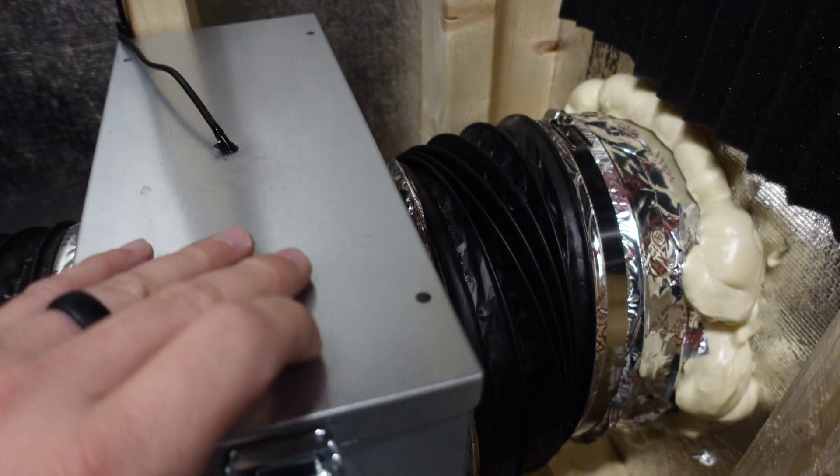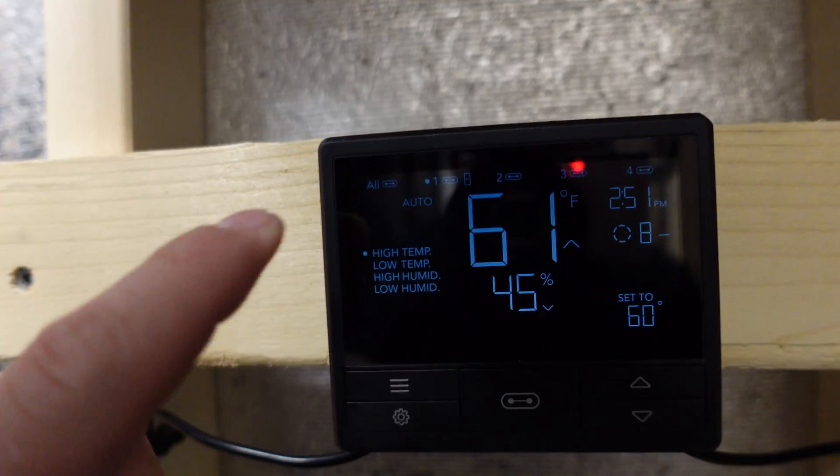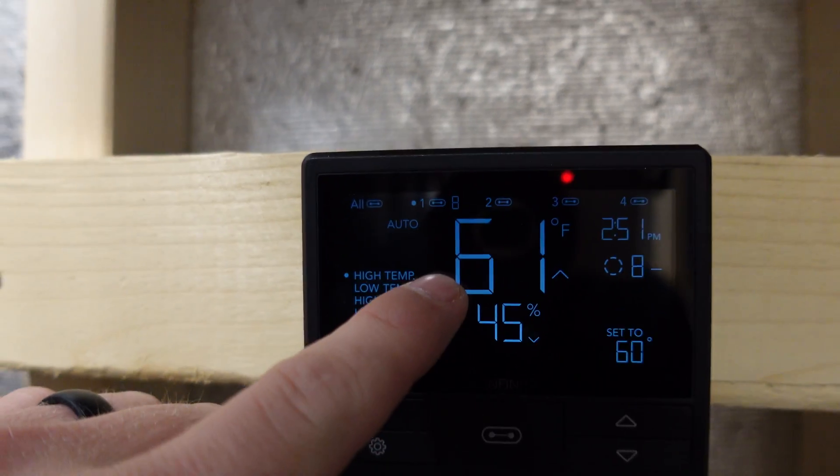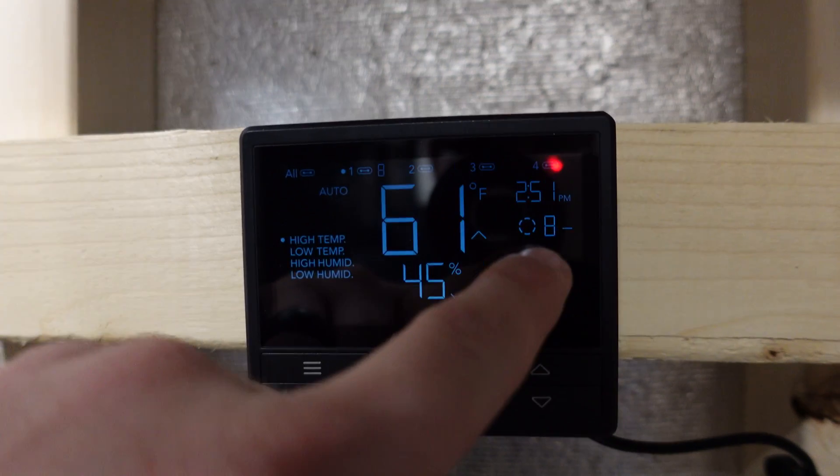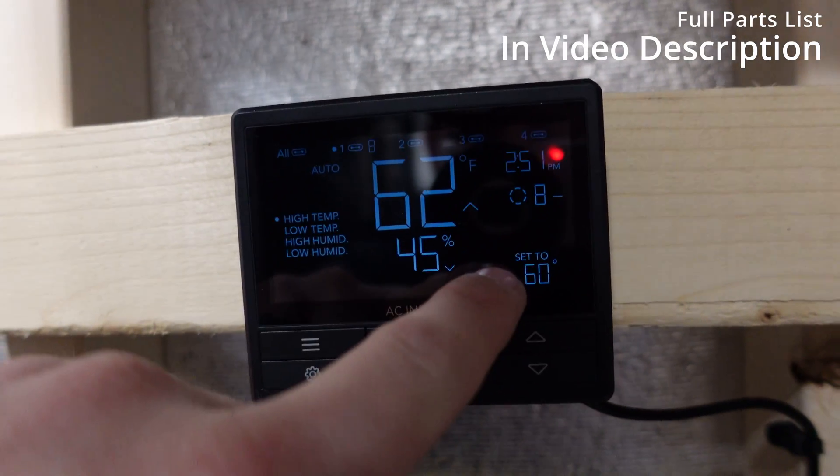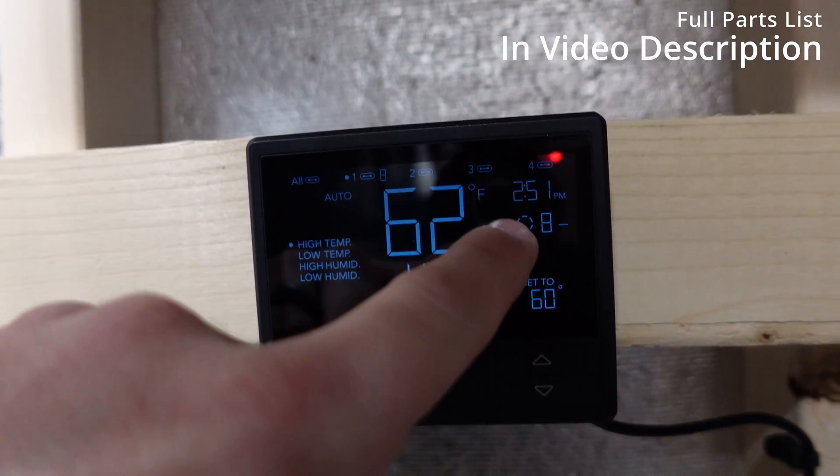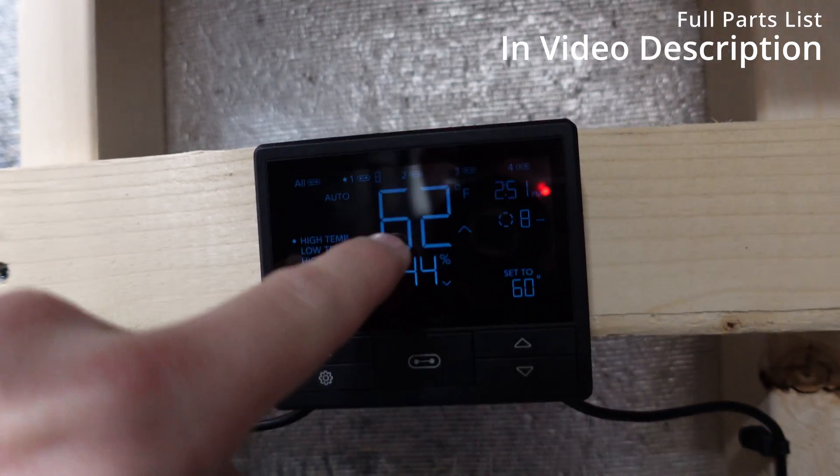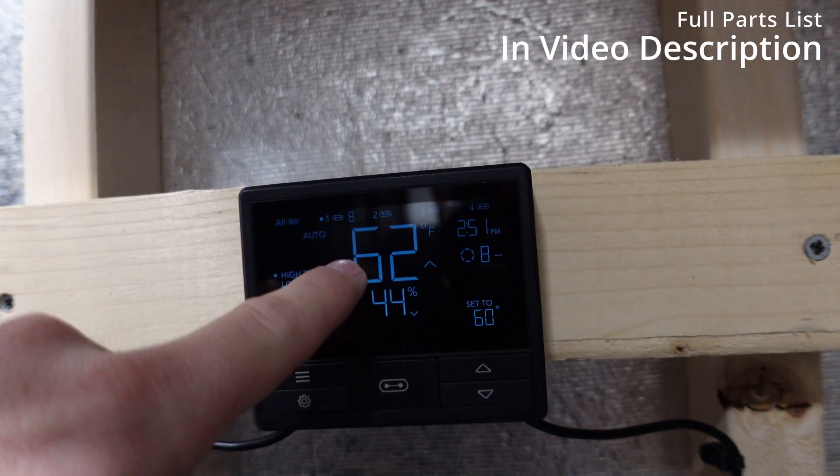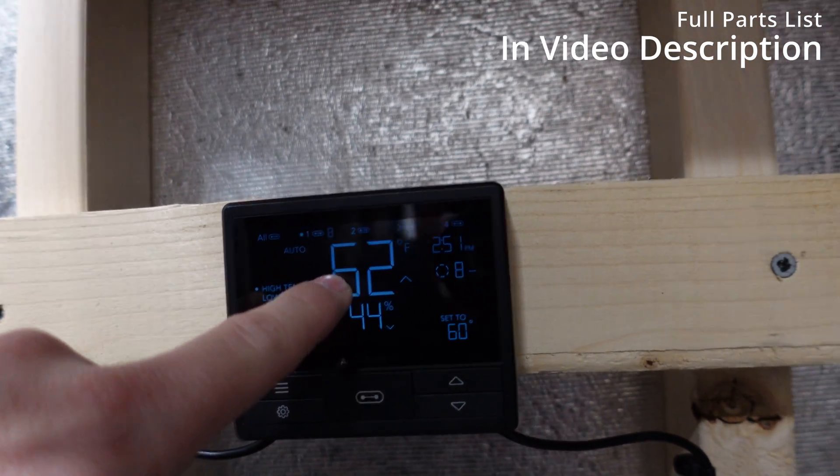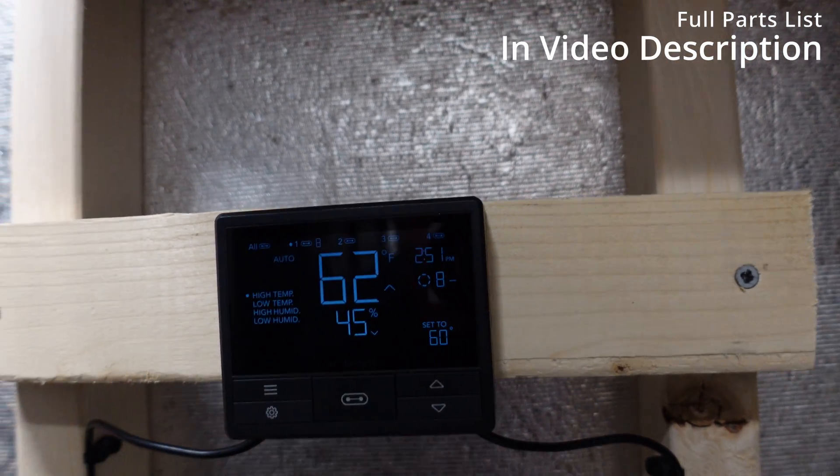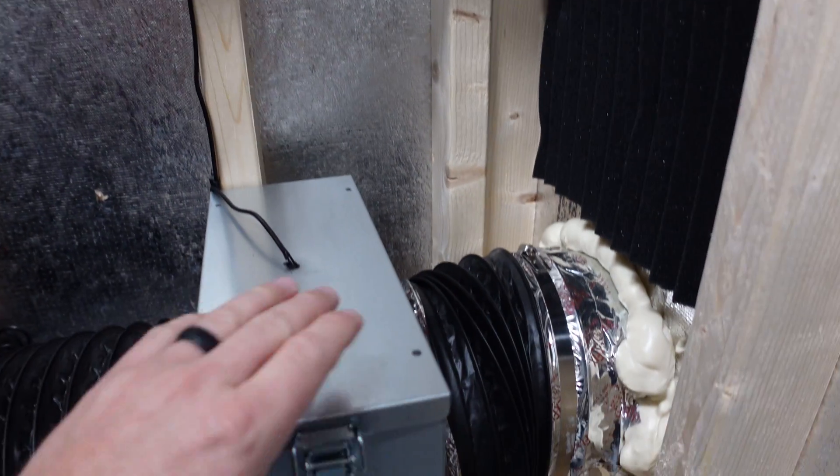And this here is our temperature probe. So, this is actually inside of our filter box. So, if I go up here, you guys can see it's at 61 outside right now. So, when it hits the temperature of 60, it goes to the speed of 8. When it drops below 60, it goes down to the speed of 5. That's how that works. And the ASIC still loves it.